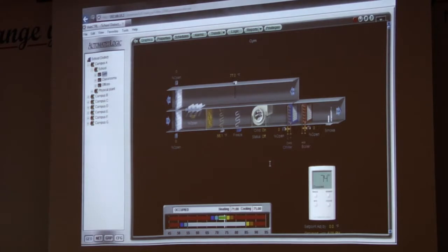All right, we got to keep the unit running. You just prove that it's running because you're just standing there. The unit's running, whatever's wrong with the current sensor, somebody has to come out and fix it. But you know that you need to get this air handler running. You have to prove that the fan is running so the rest of the system will act accordingly. So what I'm going to do here is I'm going to use a lock, but more for a long-term reason until I can get somebody in to fix it. Or I'm going to lock it for now and I'm going to go change the current sensor myself.